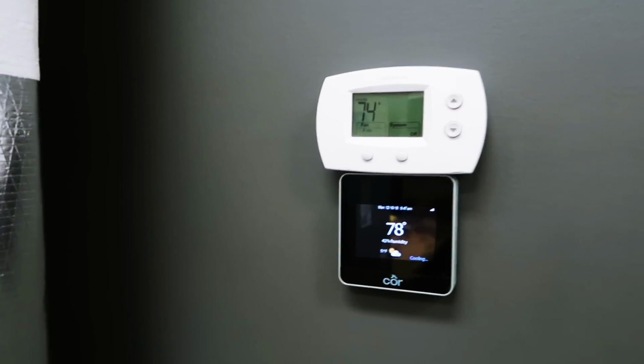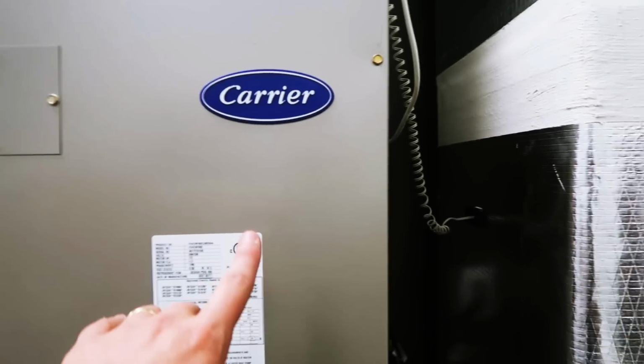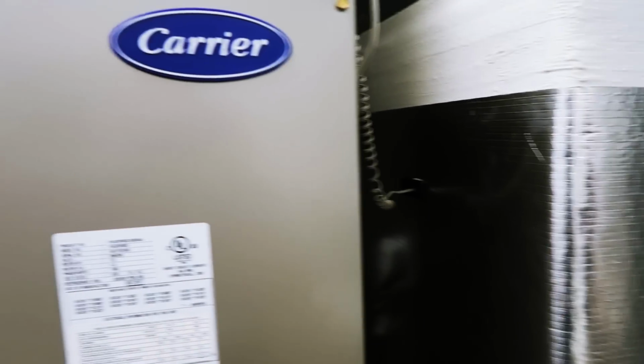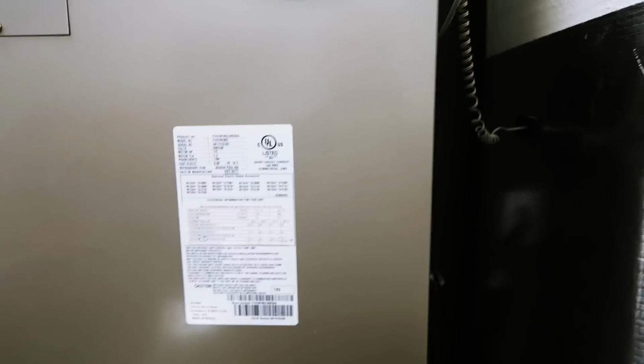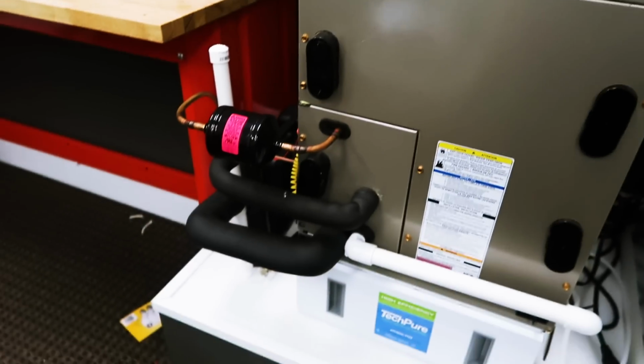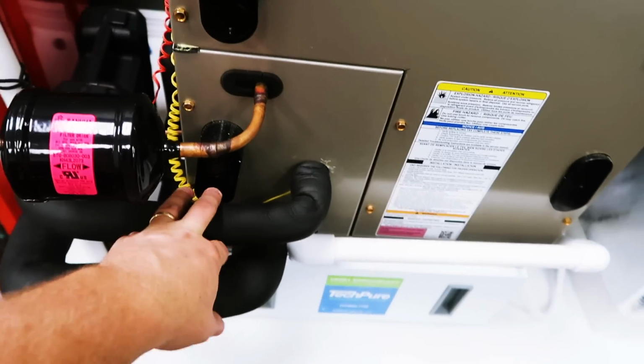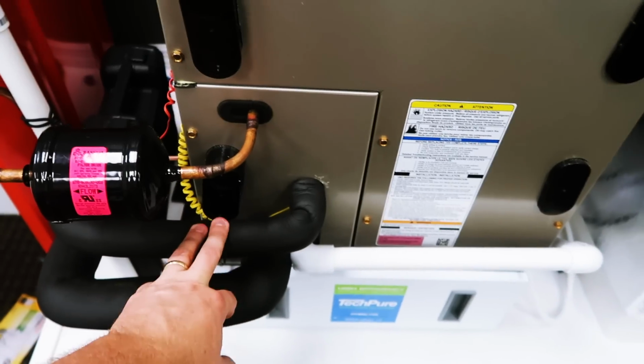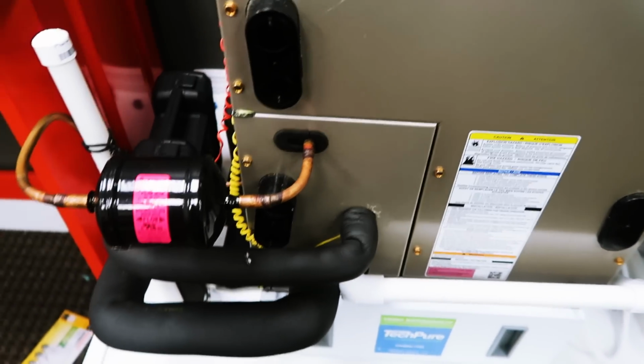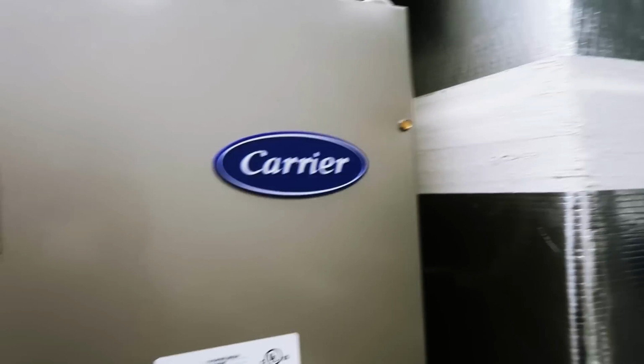But we were fast cycling the orange circuit. So in a heat pump, the orange circuit is the reversing valve circuit. This is a heat pump. And I was fast cycling it, shifting between heat and cool so that I was demonstrating the temperature change on the artist formerly known as the suction line, which then becomes the vapor or discharge line in heat mode.